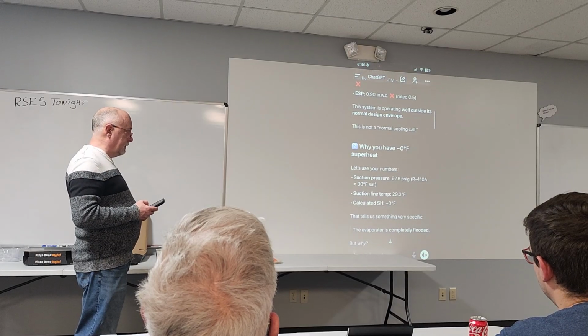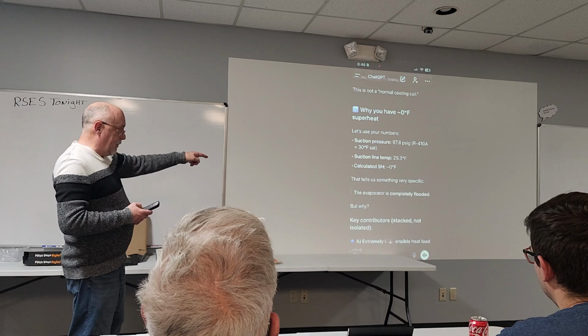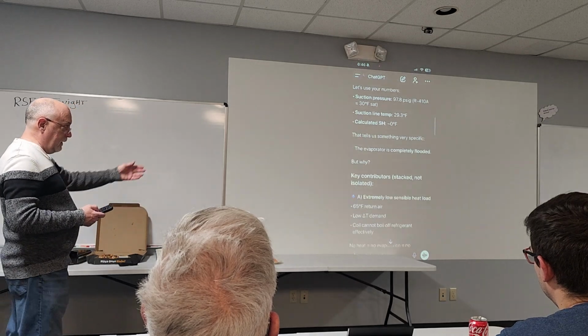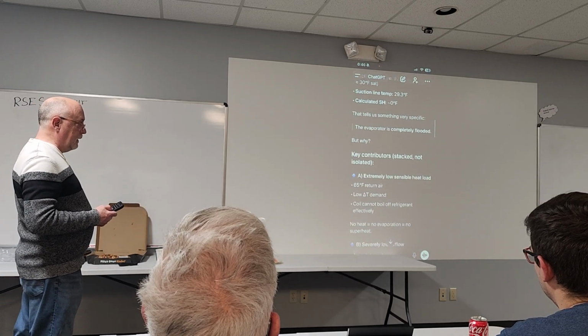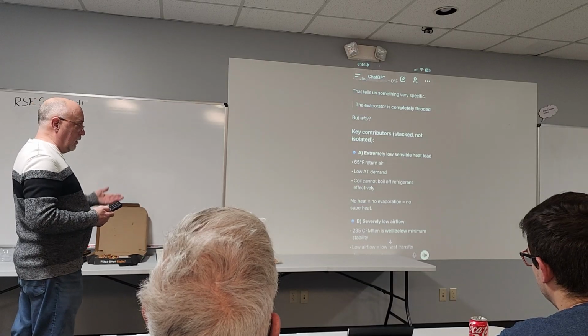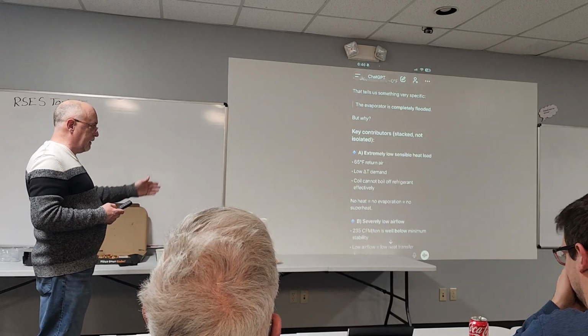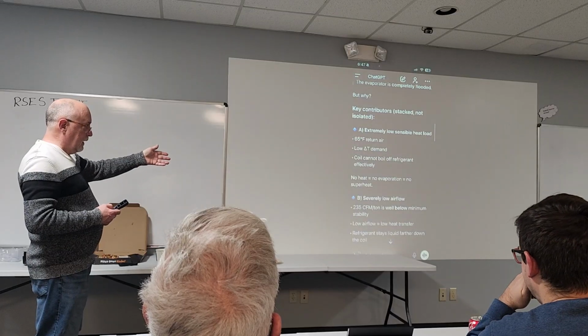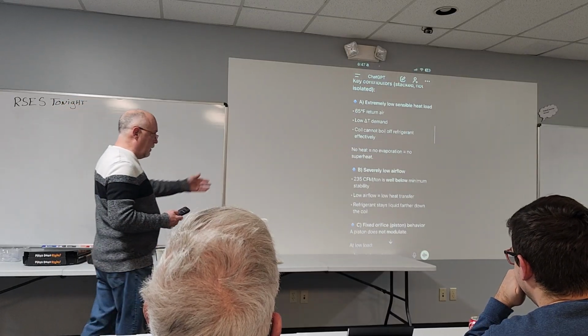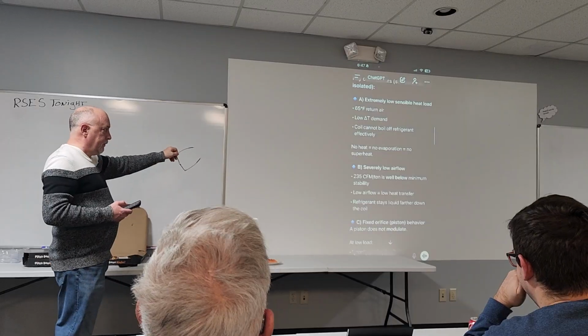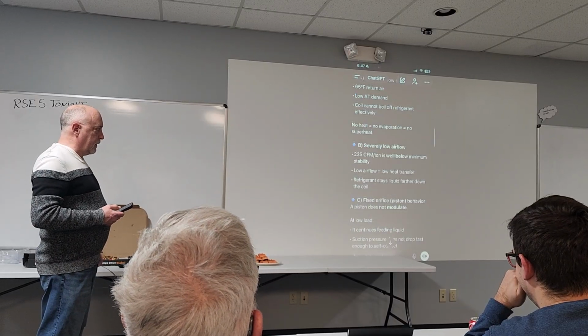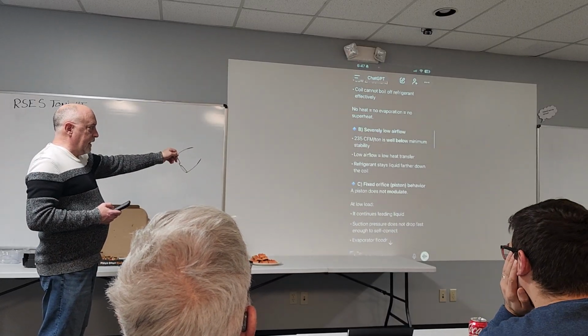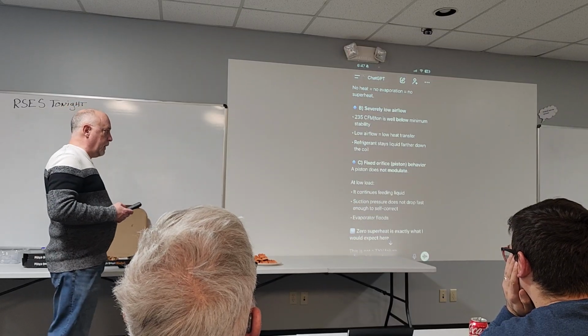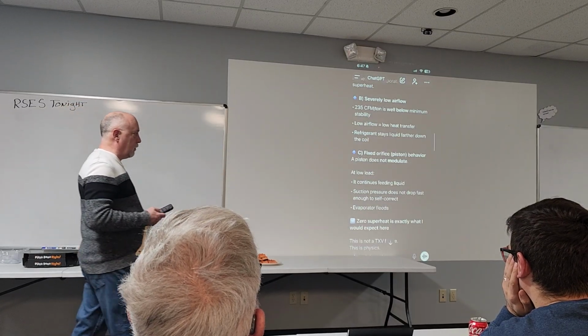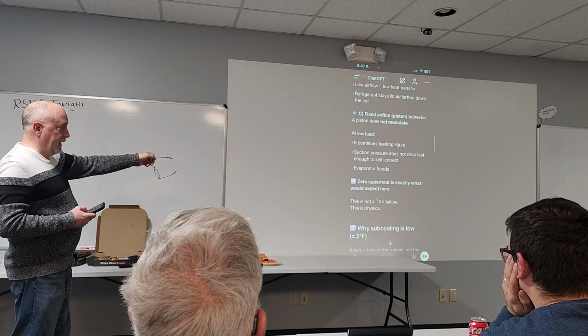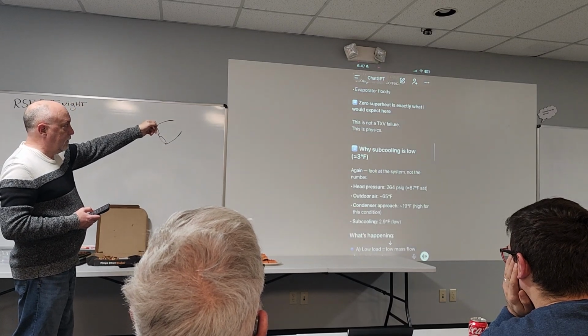Let's use your numbers. So it's calculating the superheat. The evaporator is completely flooded, but why? Contributors stacked, not isolated. So extremely low sensible heat load. You've got a 65-degree return and low delta T demand, so the coil can't boil off the refrigerant. Severely low airflow, 235 CFM per ton, well below the minimum. So low airflow, low heat transfer. Fixed orifice behavior: the piston does not modulate. At low load, it continues feeding liquid. Suction pressure does not drop fast. Self-correct, evaporator floods. That's what you'd expect. It's not a TXV failure, this is physics.